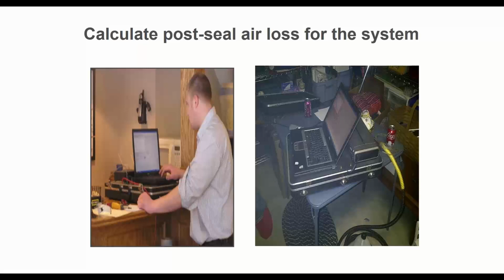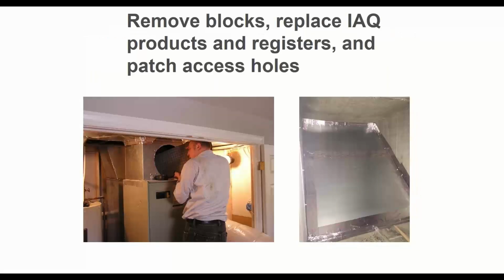Then after you're done, we do another test. So we have a pre-test to see what our leakage is, just like any duct sealing process should have. Then we're watching the duct leakage in real time. And then there's a post-test. So you're done sealing, you've concluded the project, no more sealings needed. We do a post-test to see how good we did. And then with that pre and that post-test, you can decide how much reduction you've had in leakage, because you're testing those two things at the same pressure.